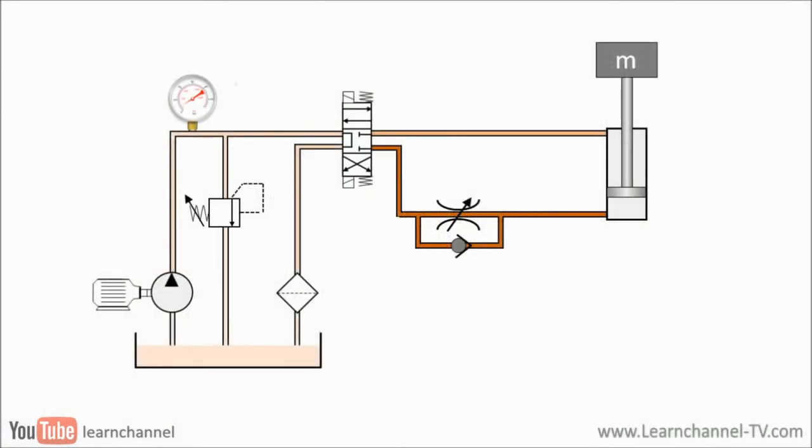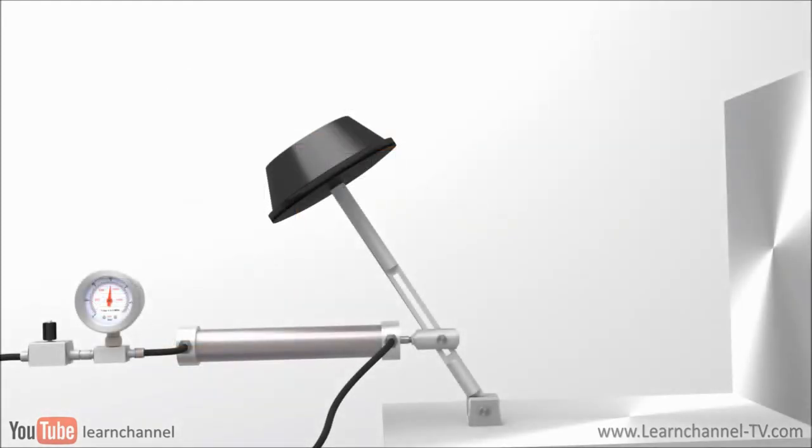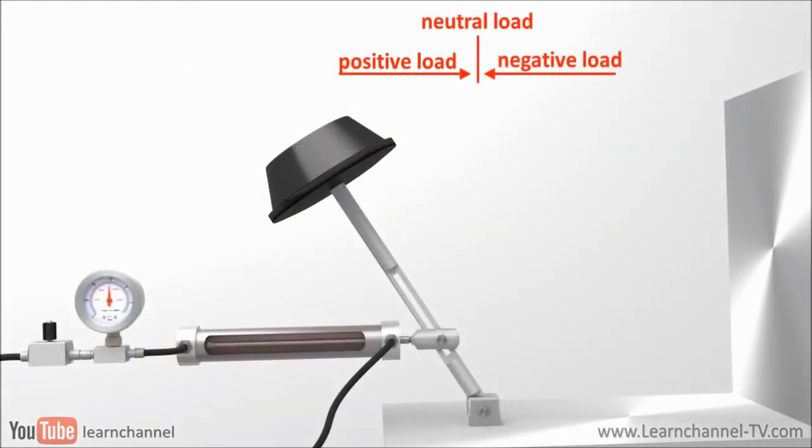But how are these flow control valves installed? One method is called meter in. Here, you control the rate of flow to the actuator. Here you see how the flow control valve restricts the volume flow when the cylinder extends.